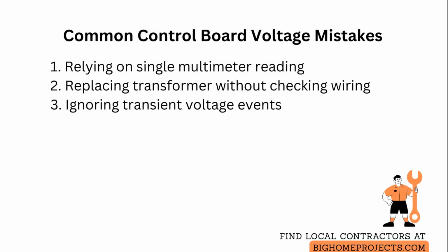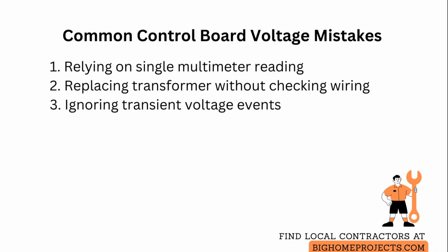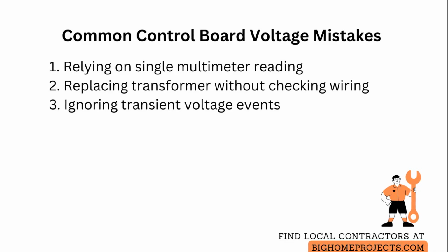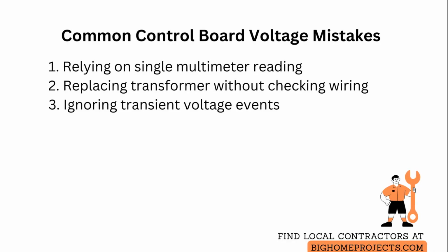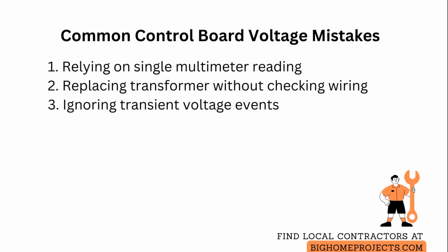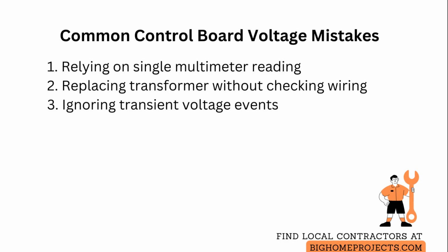A third frequent error is ignoring transient events and only checking steady-state voltage. Solution: use a clamp meter to observe current spikes and, if available, a transient recorder or an oscilloscope to capture brief, high-voltage events and correlate them with system activity.